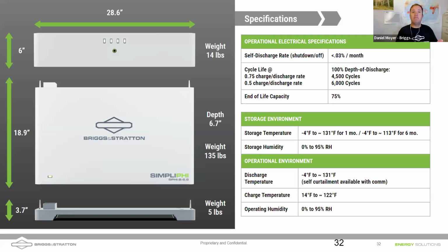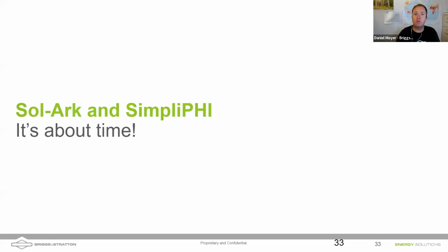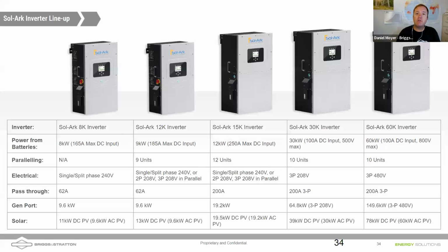Yeah, you're going to have a little more heat leaking through as well, so those are optimal conditions. I would also say that our legacy batteries, the SimpliPHI ones, do have battery warmers available if you have to go outside in a cold area. But I think this is really unique for us, because it allows us to put something in a relatively cold location and not waste energy by heating the battery. It's really cool: optimized electrolyte in the cells of our battery lets it go a little bit cooler as well. So this is the Sol-Ark line.